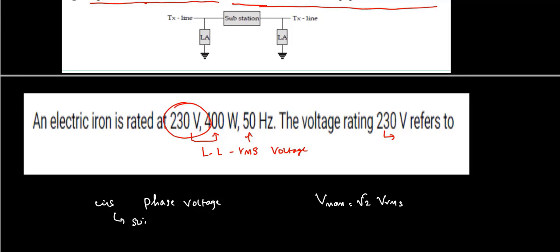The voltage that is coming from the substation, that is a line to line RMS. If he gives 230 volts, means that is a line to line RMS voltage. If he wants to design the insulation based on the phase manner, that is a phase voltage. So what is the reference voltage? It is not a line to line RMS voltage. For the design of insulation, you have to take a switch voltage. What is the switch voltage? Surge voltage. You have two over voltages, that is external over voltages and internal over voltages, that is switched voltages.